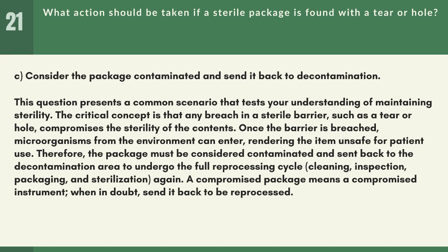Answer: C. Consider the package contaminated and send it back to decontamination. This question presents a common scenario that tests your understanding of maintaining sterility. The critical concept is that any breach in a sterile barrier, such as a tear or hole, compromises the sterility of the contents. Once the barrier is breached, microorganisms from the environment can enter, rendering the item unsafe for patient use. Therefore, the package must be considered contaminated and sent back to the decontamination area to undergo the full reprocessing cycle: cleaning, inspection, packaging, and sterilization.